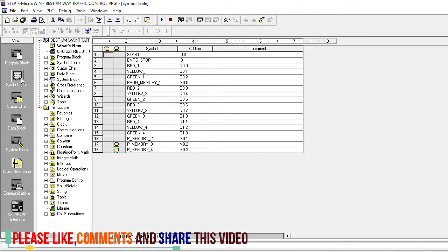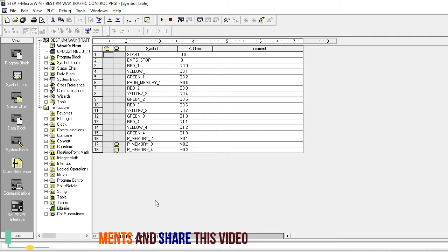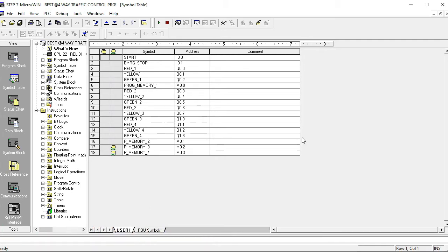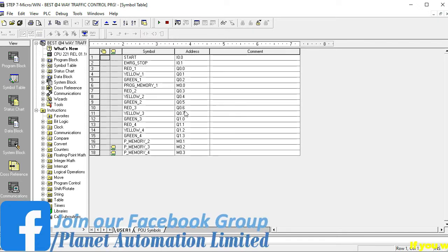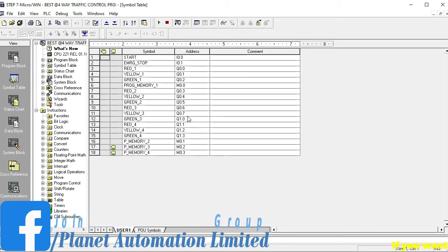First I want to describe what devices we are using in this programming sequence. The instructions are: start is I0.0, emergency stop is I0.1, red is Q0.0, yellow is Q0.1, green is Q0.2, and M0.0 is the program memory. We firstly use red, yellow, green for the first road. The second road red, yellow, green uses Q0.3, Q0.4, Q0.5.